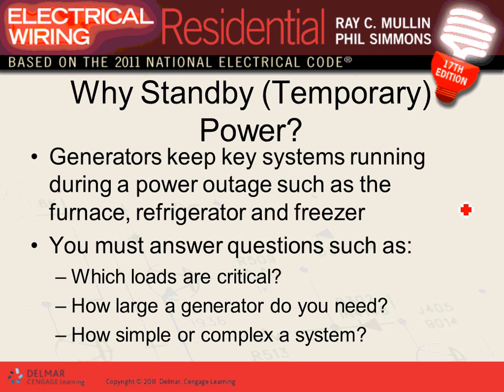Why standby generators running during? So the most important thing for standby generators. Now I want to remind you, we're doing dwellings, as in single family dwellings, which do not require an emergency system. Now, if you have an apartment building, they require you to have an emergency lighting system. A lot of apartment buildings solve the problem, guys, by having bug eyes. Bug eyes are battery operated lights. They give you, what is it, an hour and a half or something of light upon the loss of power, so people can exit the apartment building. They put them in the hallways and stairways. But for single and double family dwellings, you don't need an emergency system.